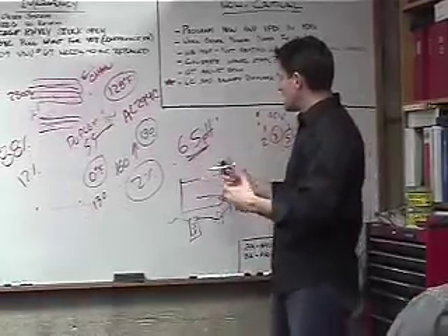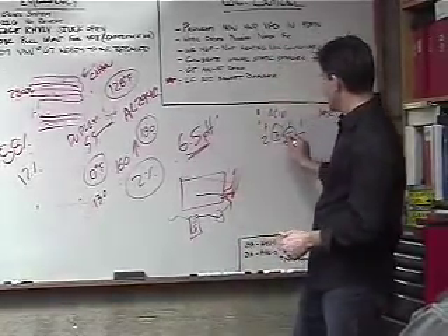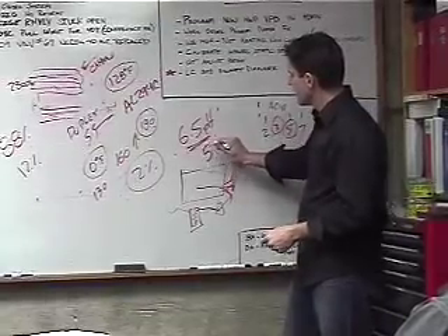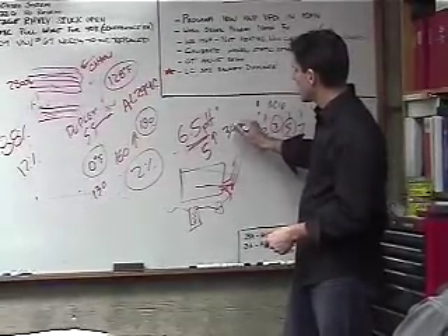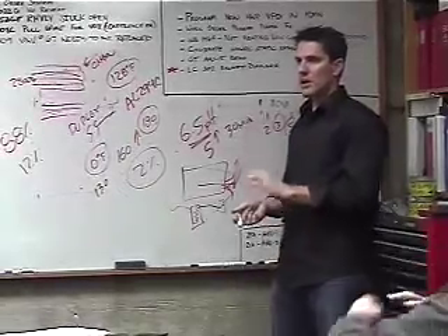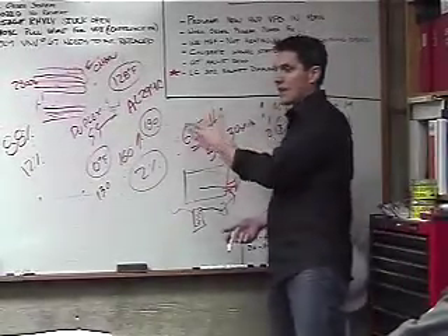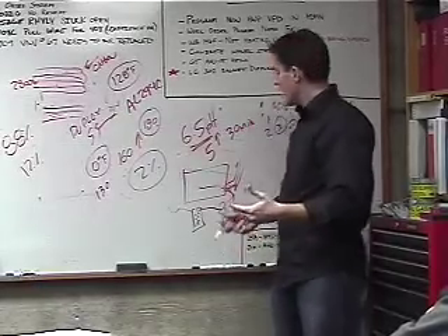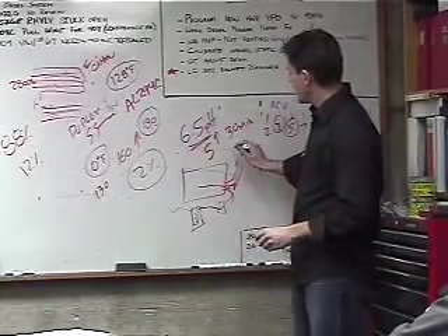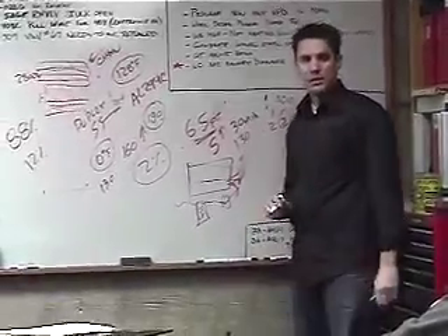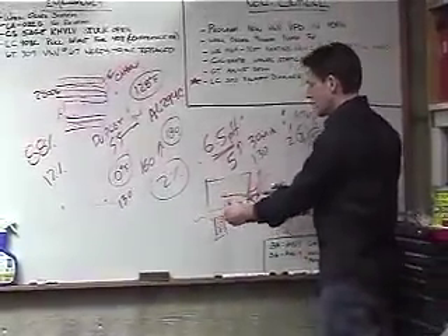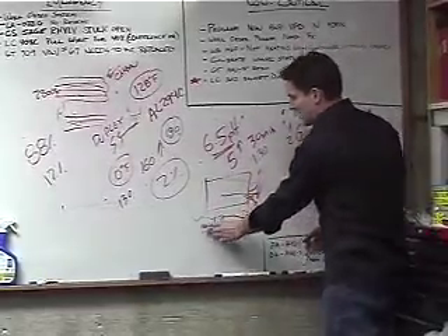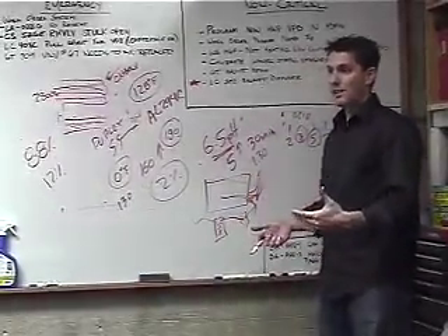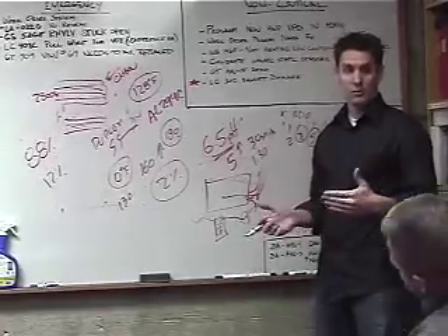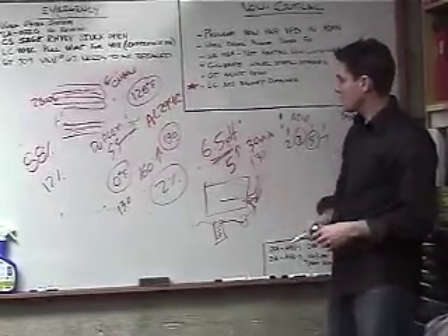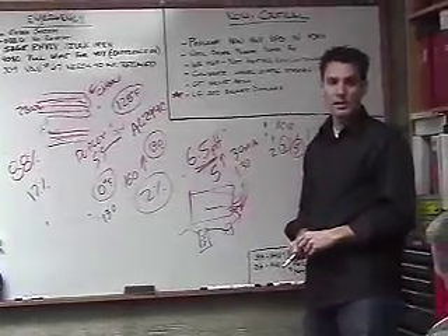The typical sizing for this, to get your pH to go from 5 up to 6.5, needs about a 30-minute contact time. So as long as you've got good lime rock deposits, 30 minutes on that lime rock will give you the neutralization that you need. If you're at 3, then you're going to need about an hour and 30 minutes of contact time. That's usually how we size this based on the boiler. You should have a basin that's large enough, but if over time you realize we're pushing more condensate through here than we normally would, you might not be getting the neutralization that you want, so you better put in a little larger basin.